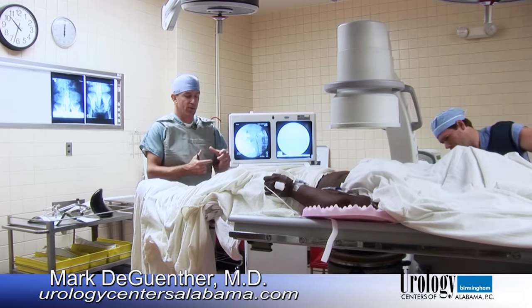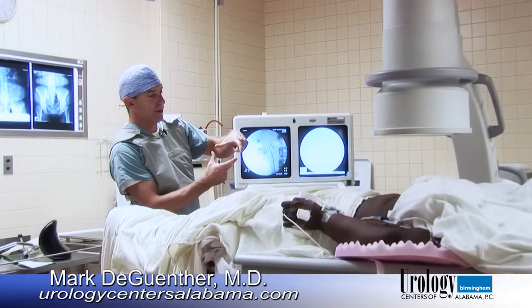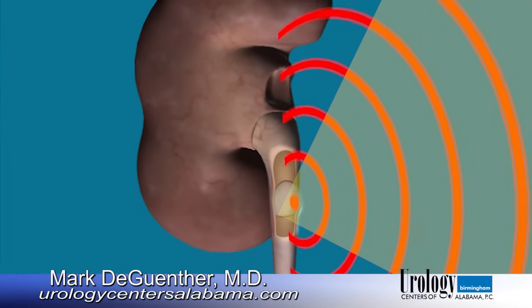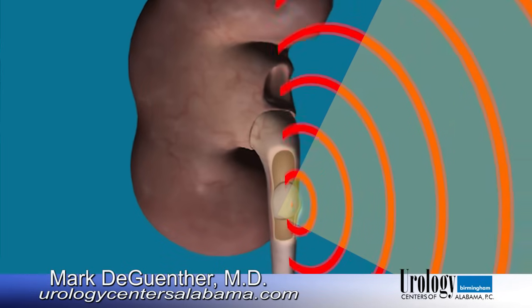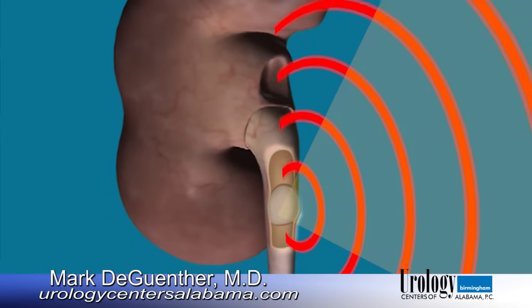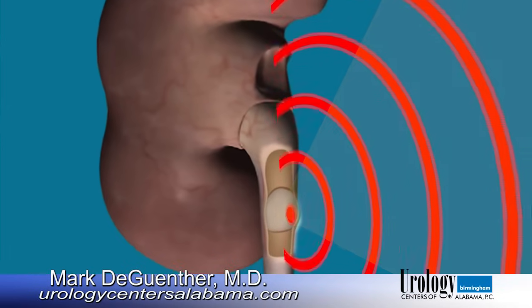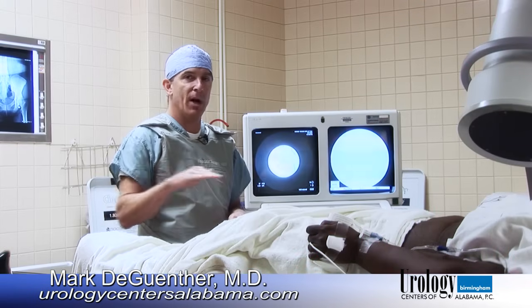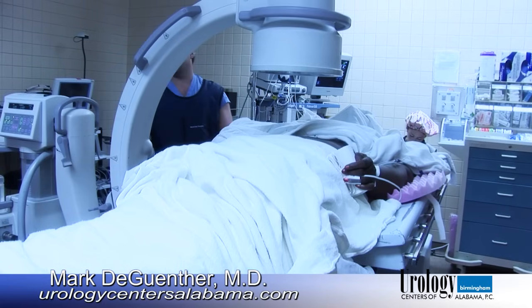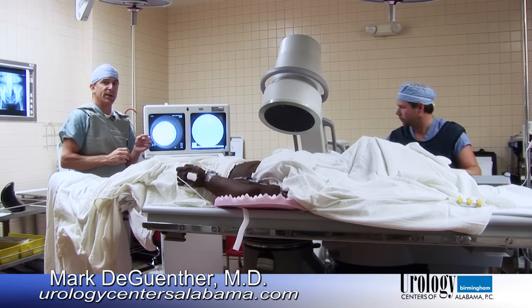As the shockwave comes through the skin, it travels in a pattern about this big. As it approaches the level of the stone, it is focused down in a cone where all of the energy is directed directly at the stone. The patient is lying on a table that moves up and down, back and forth, and we adjust it in three dimensions so that the very tip of that cone is centered on the stone.